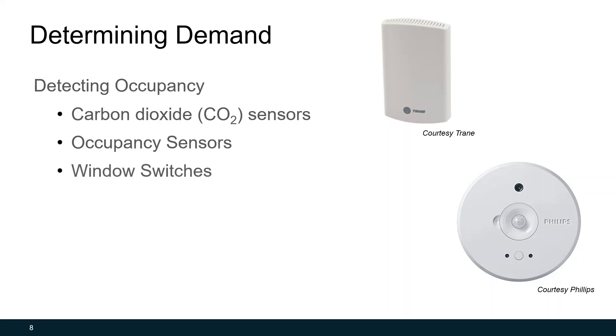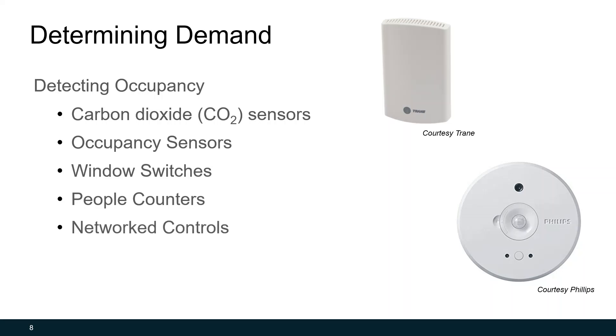There are some other sensors we can use. Window switches are used if you have operable windows — if you want to automatically open your windows when it's suitable outside to naturally ventilate your building, you can use window switches. You can also use people counters, and these come in a number of forms and are somewhat of an emerging technology. These range from infrared scanners to using your security system if you can make it cyber secure — when you badge into a facility, you count the number of people in your building. There's even more emerging technology around network controls; one example is using the Wi-Fi router to detect the number of devices and estimate how many people are in the building or in a space.